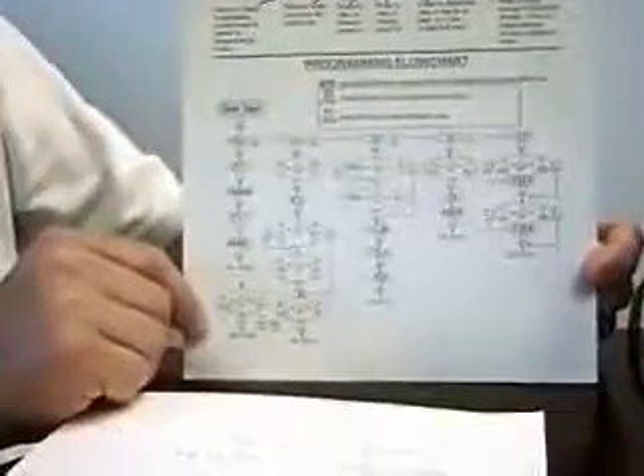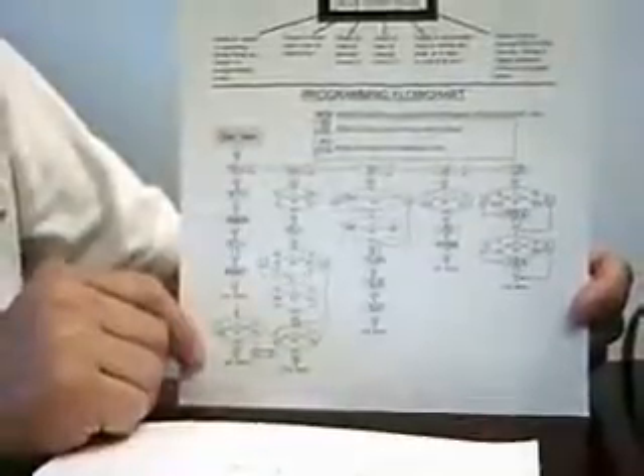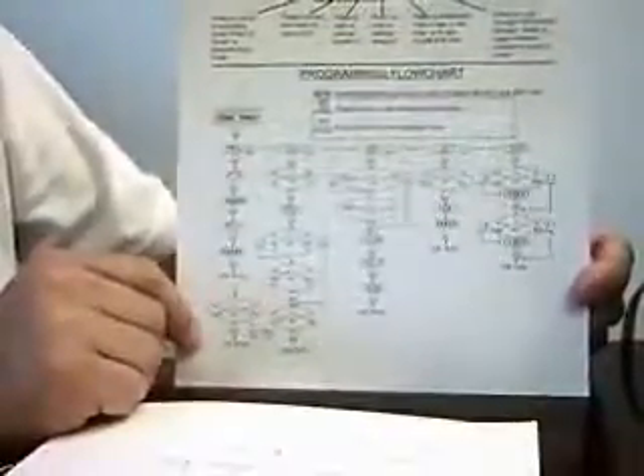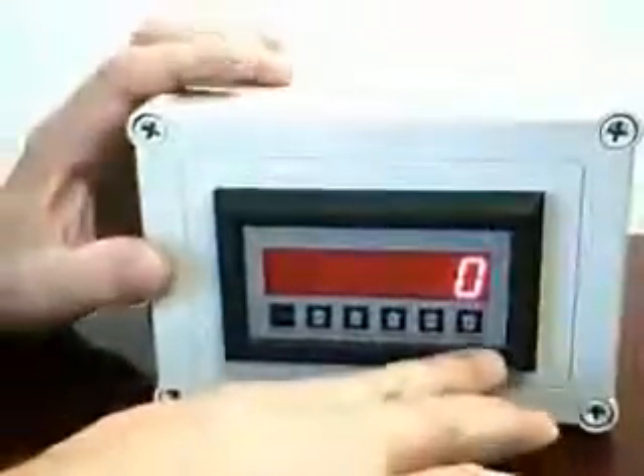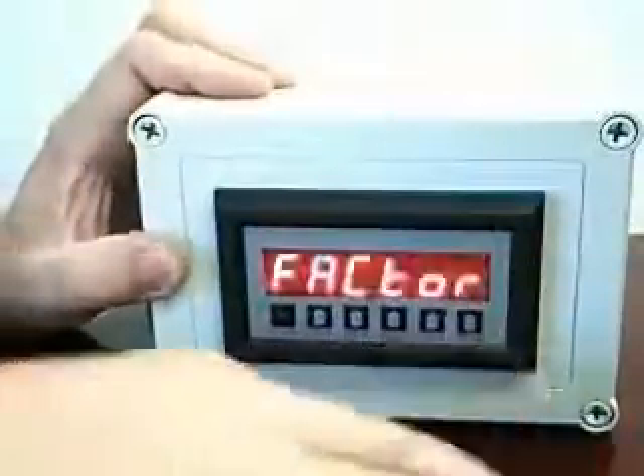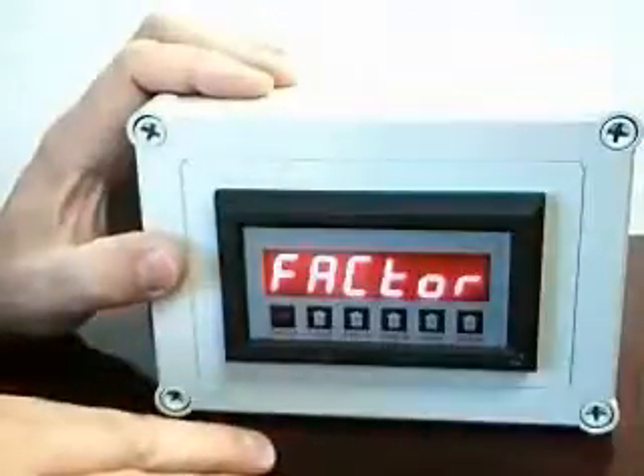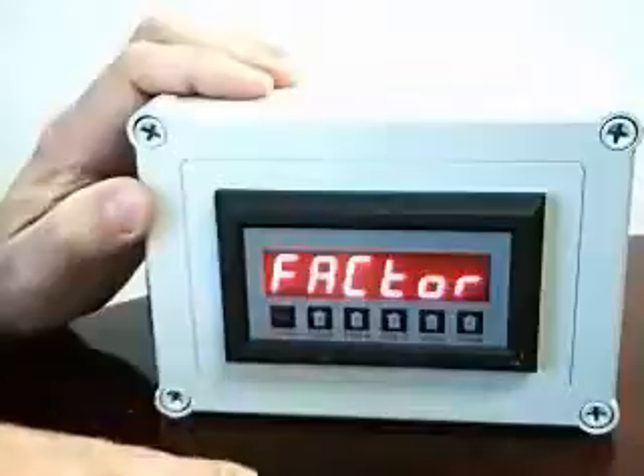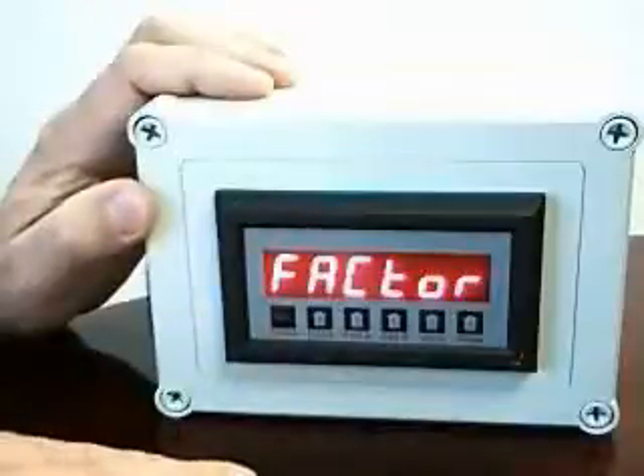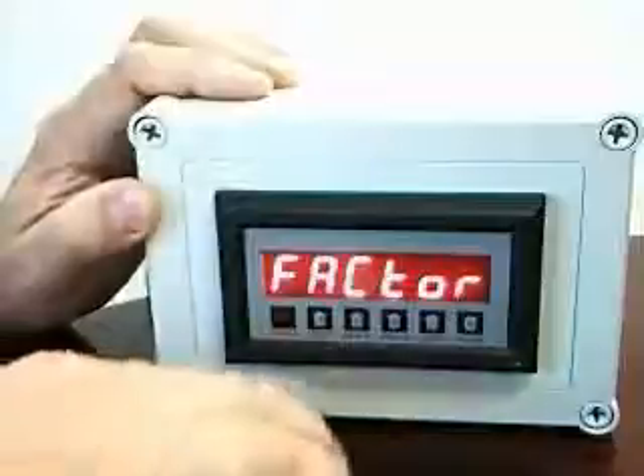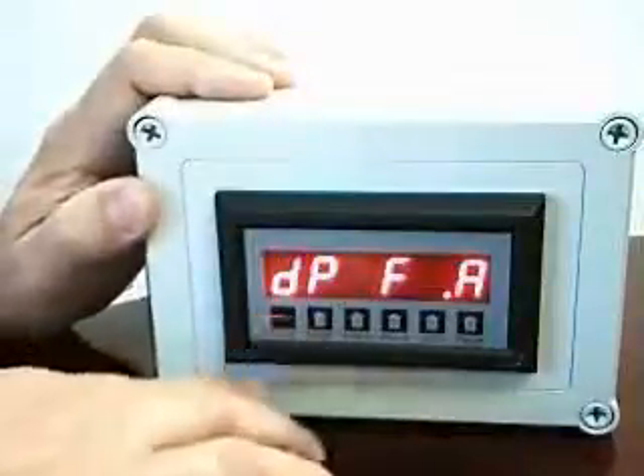I would like you to follow along on the menu again on page 7 as we now go through the basic configuration of this instrument under the assumption that we want to read in gallons per minute and whole gallons on the display. We begin with an unlocked unit by pressing the program button. The unit responds to the first key depression by displaying a message that it's at the point where it's going to show you the factor group. By pressing Enter, it goes to the first menu.